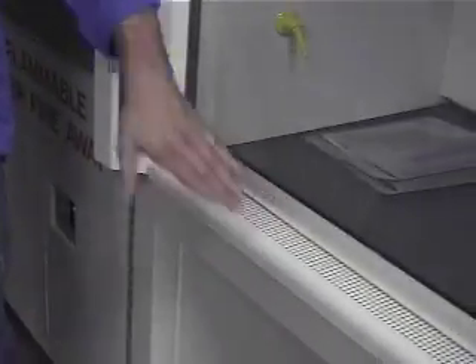That's a common problem in most lab scenarios. They leave the hoods open all the time. You're wasting exhaust because your fans are running up higher. If you can get your users to keep these closed, then you can keep your flows as low as you can, and your ZPS doesn't need to do anything. It'll still tell it to go to standby, but it'll already be at its minimum, so you won't get down to that 60 because it can't go below its minimum. But that's your best energy savings, is close the sashes.